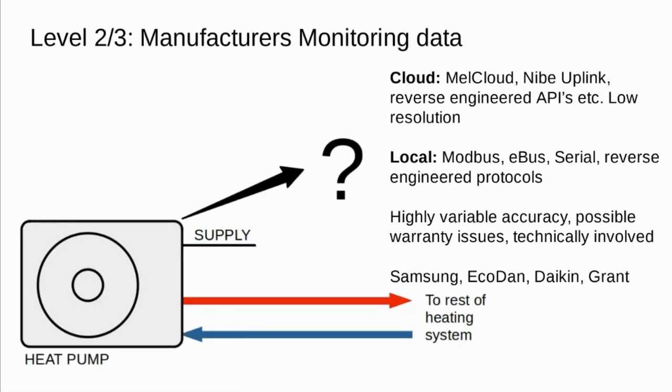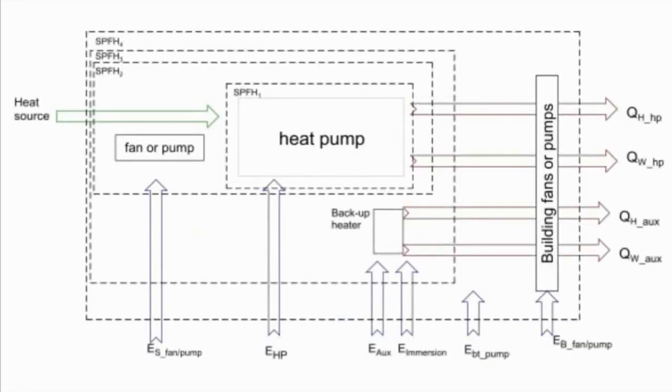Because heat meters come with a matched pair of temperature sensors that have been tested in the factory and calibrated to be totally identical. Especially when the delta T, the difference between flow and return, is quite small, if you're out by even half a degree, that could be like a kilowatt of heat difference, which is quite considerable.